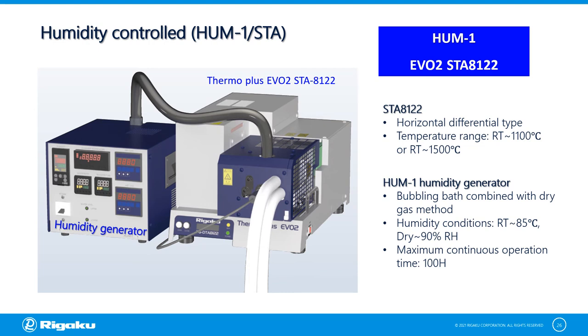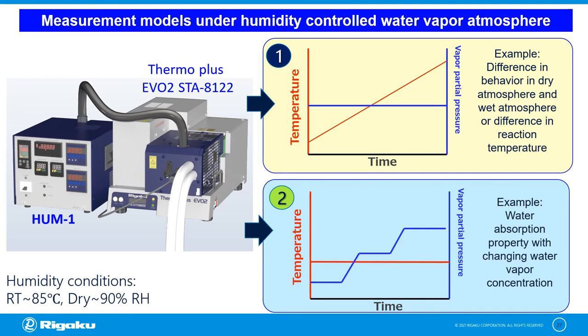In STA, we can perform measurements under air static or with a gas flow using inert or air atmosphere. However, if you want to measure the effect of relative humidity on the thermal behavior of a material, the HUM1 humidity generator is a suitable option for simulation measurements using water vapor atmosphere. The relative humidity can be controlled ranging from room temperature up to 85°C, dry to 90% RH, with a maximum continuous operation time of 100 hours. This option can be connected to an STA, TMA, or even evolved gas analysis systems. Using the HUM1 option, there are two major measurements that can be performed: keeping the relative humidity constant at a constantly changing temperature, or keeping the temperature constant at a constantly changing water vapor concentration.